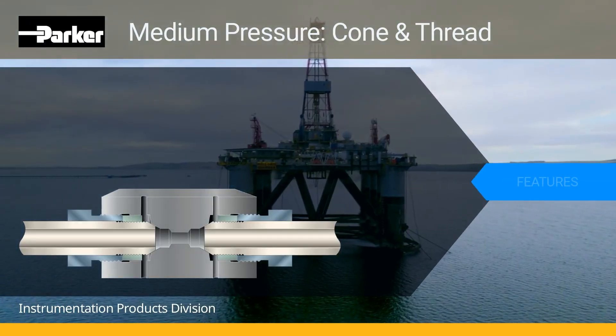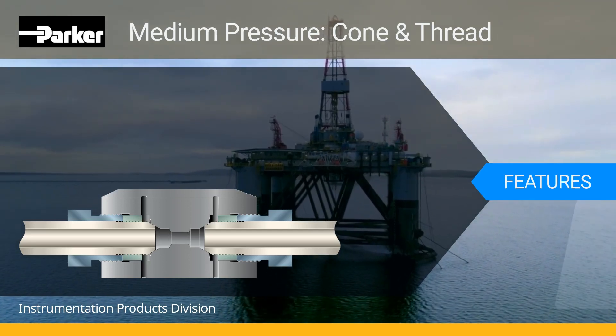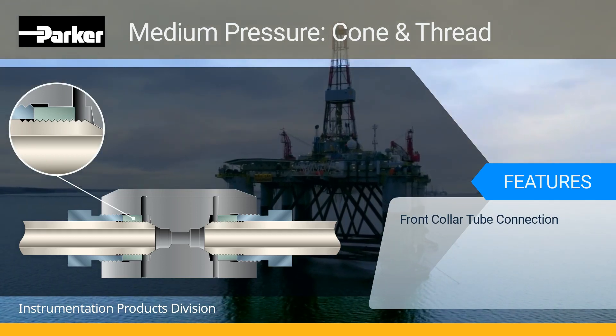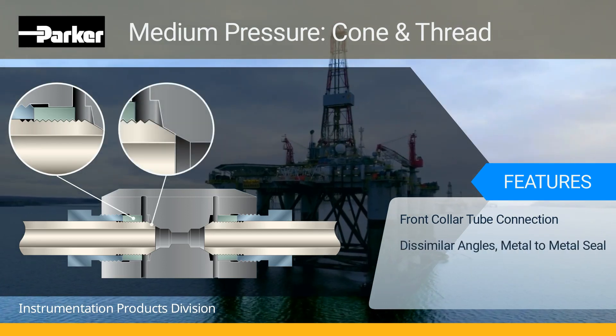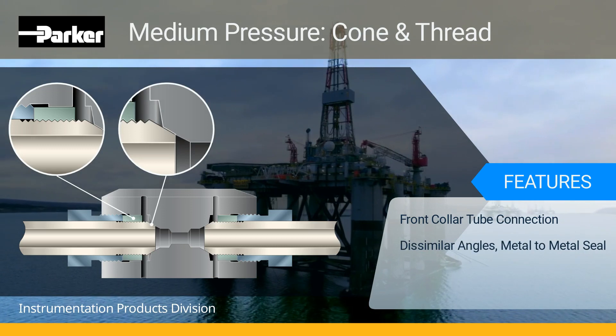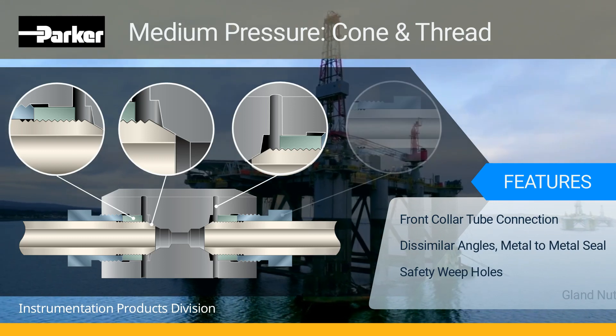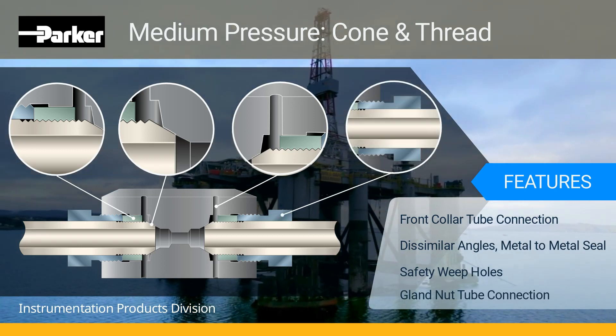Here are some of the unique design features found in the Parker Autoclave Medium Pressure Cone and Thread Fittings. The collar is positioned in front of the gland to secure the tubing into the connection while keeping port size and fitting width to a minimum. Dissimilar angles, the tubing cone and fitting interior form a metal-to-metal line seal within. Implementation of safety weep holes to prevent tube extraction, and the gland nut mechanically holds the tubing into the connection using a predetermined torque value.